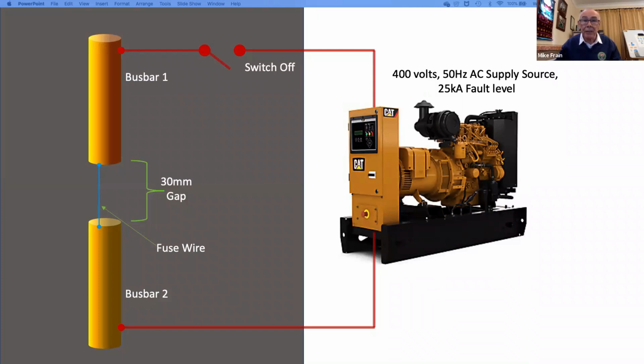So here we are. If you have a look in the diagram, you can see two copper bus bars that are separated by a 30mm air gap. And then they're connected to a 400 volt electrical source with a prospective short circuit capacity of 25,000 amps.